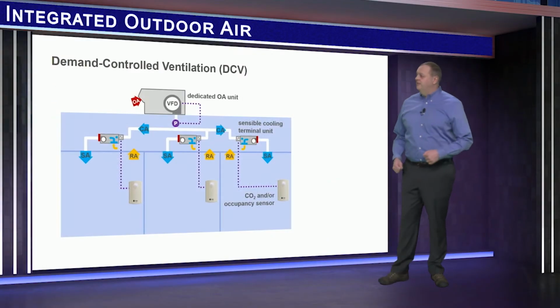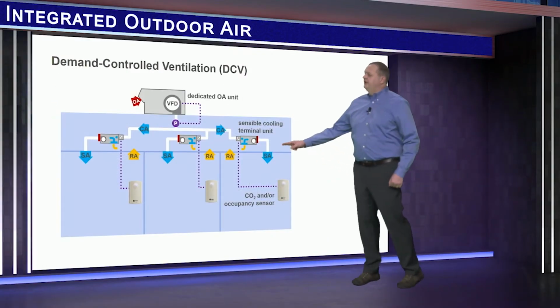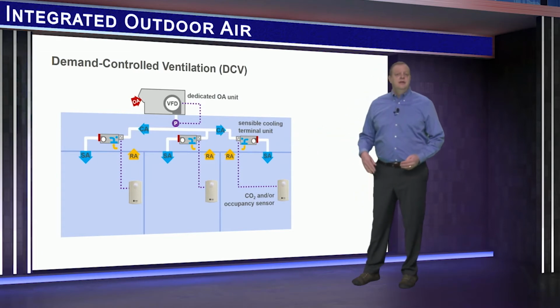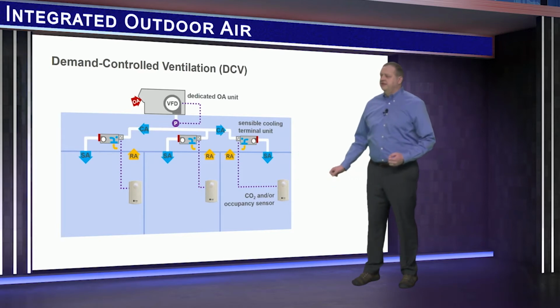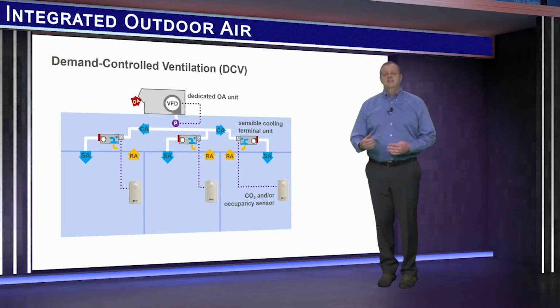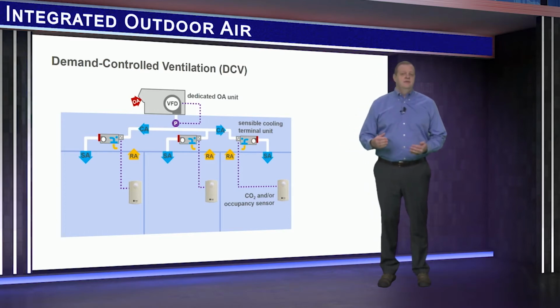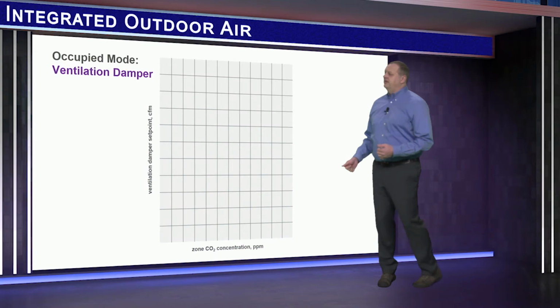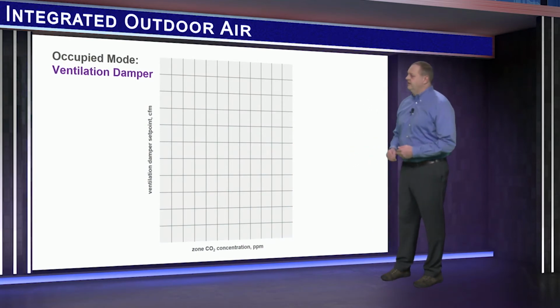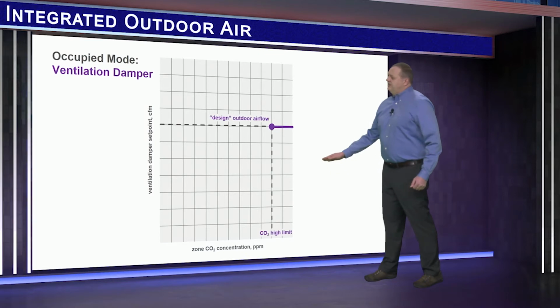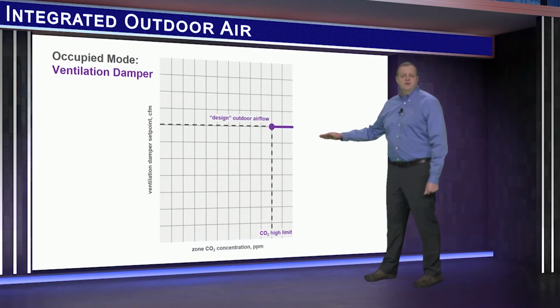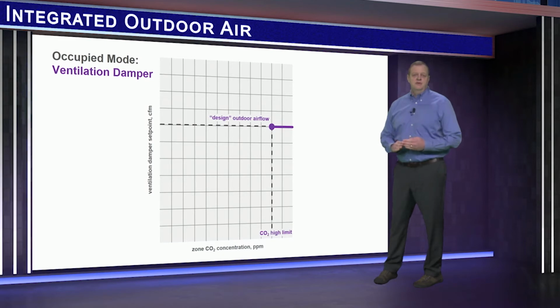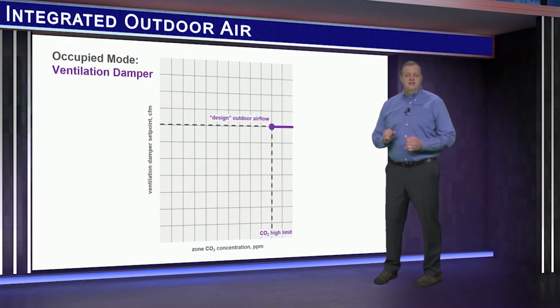Well, since 100% outdoor air is delivered to an airflow measuring damper in each terminal unit, implementing demand control ventilation is very straightforward. When a zone CO2 sensor is connected to the controller, the demand control ventilation sequence will dynamically adjust outdoor airflow by modulating the ventilation damper based on the current CO2 concentration measured in the zone. Now, this chart depicts how the ventilation damper responds. When the zone CO2 concentration is at the high limit, the ventilation damper is controlled to bring in the design zone outdoor airflow. This is what the code requires at design zone population.